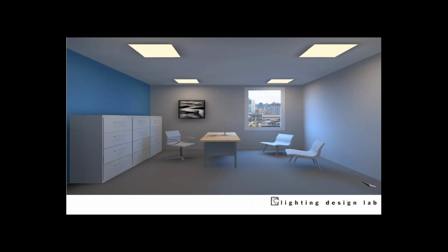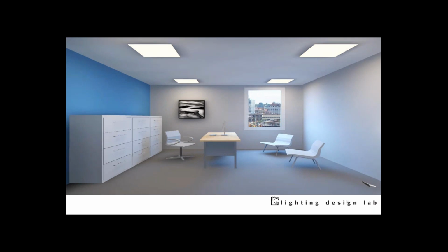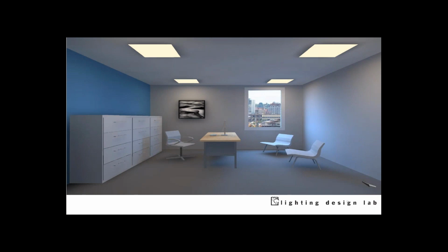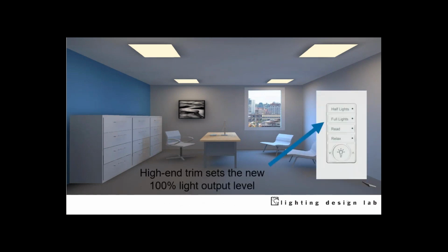So isn't this a lovely looking office? It looks just right, and I'm guessing there's a beautiful water view right out that window. Here we imagine the new lights just got installed, and it's like, boy, that's pretty bright and glary. Let's tune it down. Nope, way too dim. Bring it up. We're going for 30-foot candles on the surface plane for this office. Boom, we reached our target level. And when you reach that target level, you've done your high-end trim.